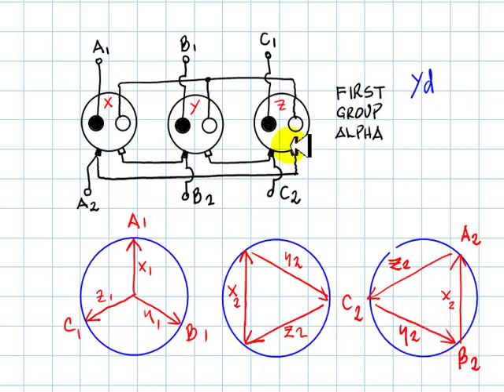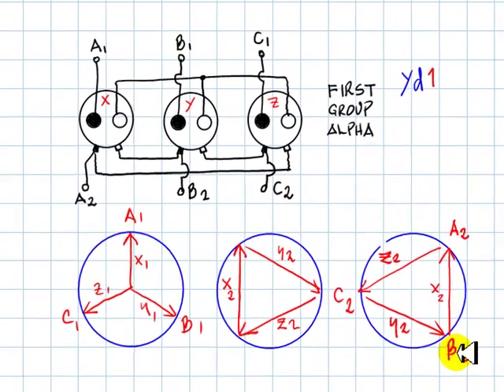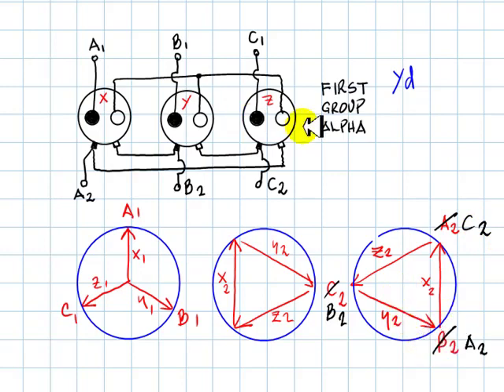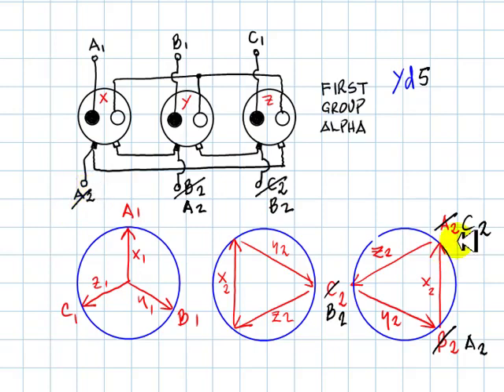Y2 tip is B2, Z2 tip is C2. We realize this is not a standard convention as written, giving YD1. However, without changing the wiring — just by relabeling the secondary phases — we can call the tip of Y2 phase A2, the tip of Z2 phase B2, and the tip of X2 phase C2. With the same wiring, this gives a compliant YD5 connection.